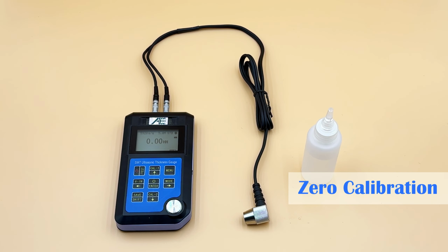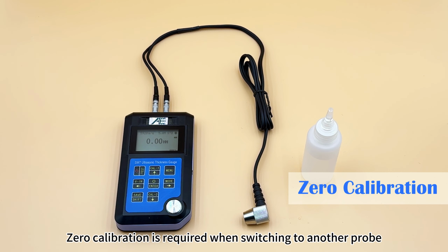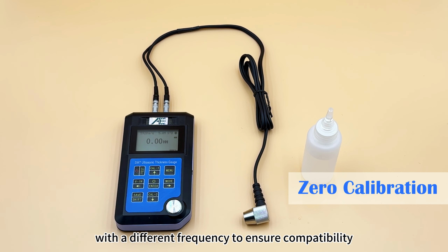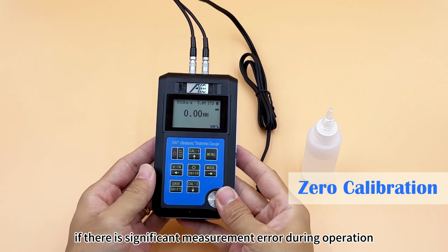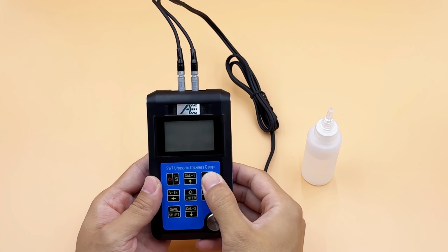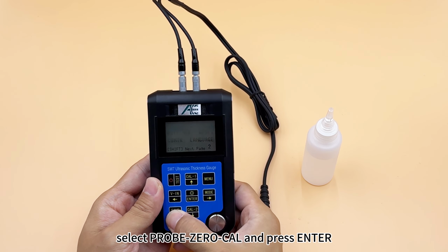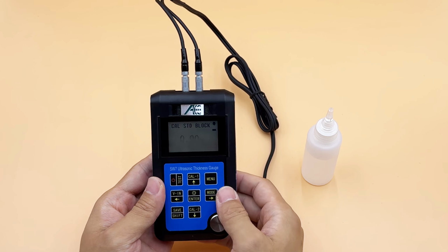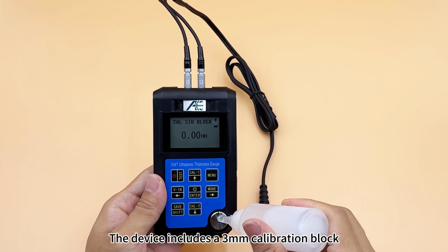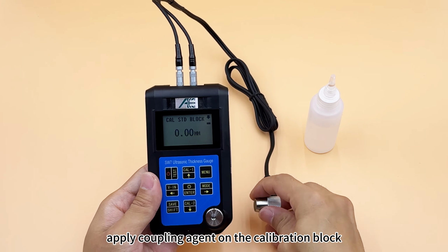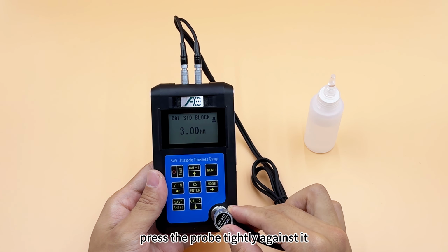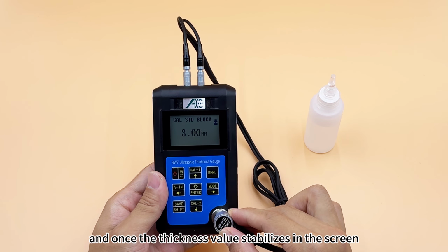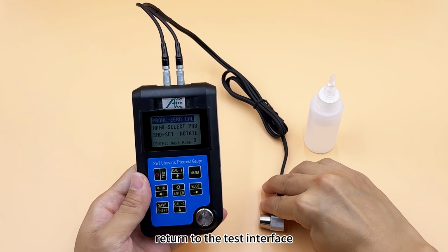Basic measuring operations. Zero calibration. Zero calibration is required when switching to another probe with a different frequency to ensure compatibility between the device and the probe. Zero calibration can also be performed if there is significant measurement error during operation. Press menu and shift key, select probe 0 cal, and press enter. The device includes a 3 mm calibration block. Apply coupling agent on the calibration block, press the probe tightly against it, and once the thickness value stabilizes in the screen, return to the test interface.